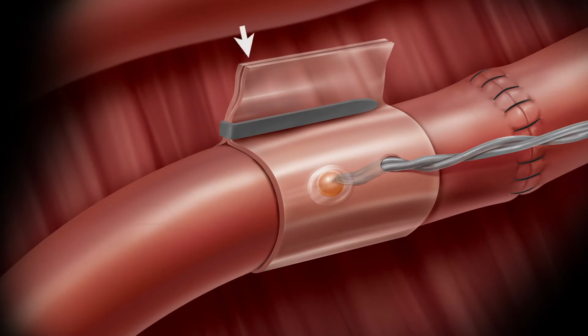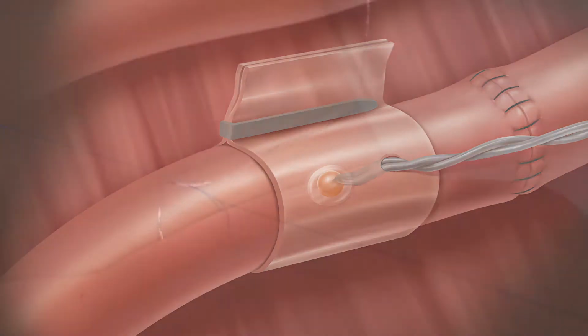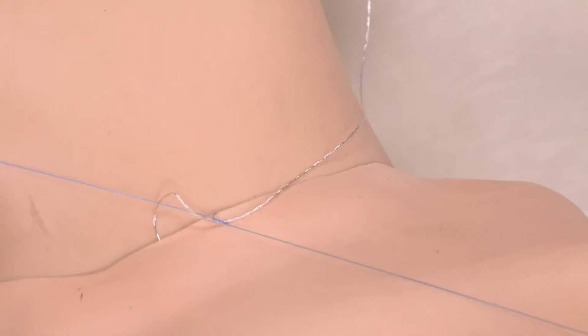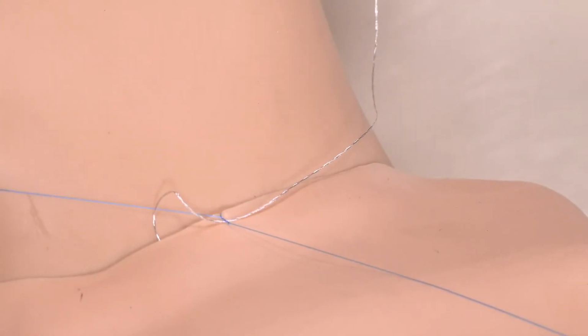Trim the curved silicone cuff to accommodate the vessel size. Ensure the transducer assembly is directed toward the targeted vessel. Secure the free ends of the silicone cuff together around the target vessel using appropriate sutures or a clip to maintain the cuff's position.